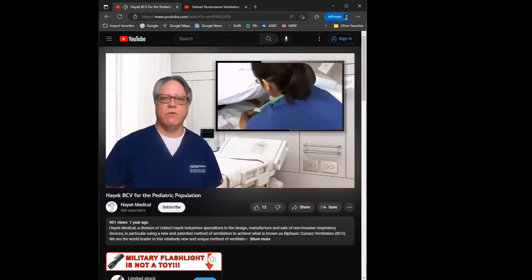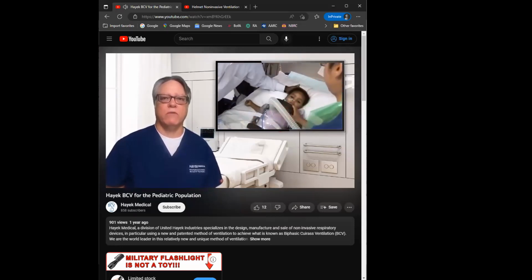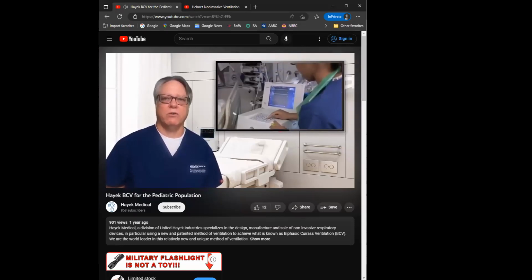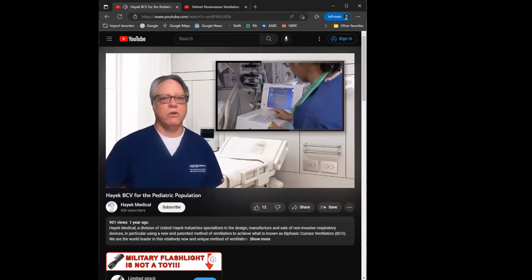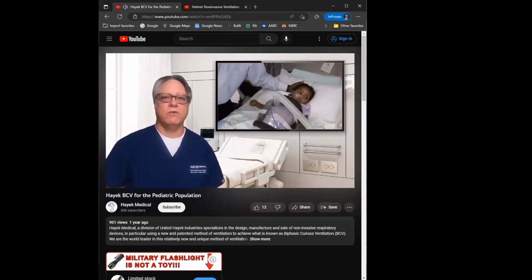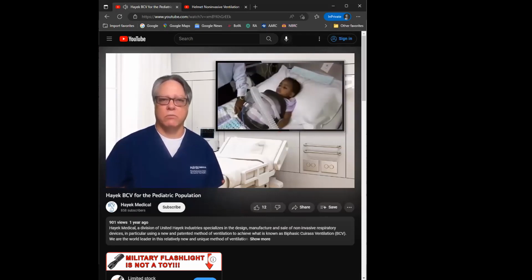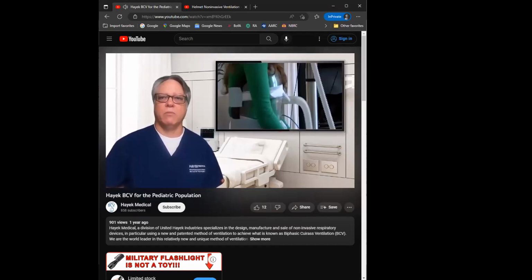In this much refined version of negative pressure ventilation only available with the Hayek RTX ventilator, a chest shell or cuirass is placed over the patient's chest and abdomen and the pressure in the cuirass controlled. BCV can serve as non-invasive ventilation, a lung recruitment tool, and a means of airway clearance and cough support.